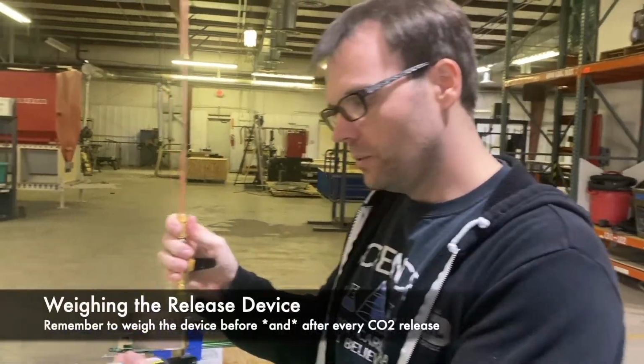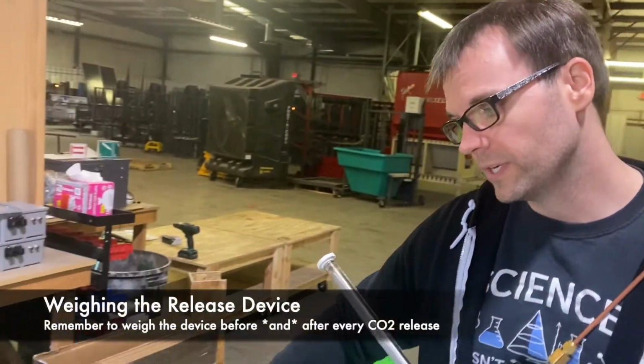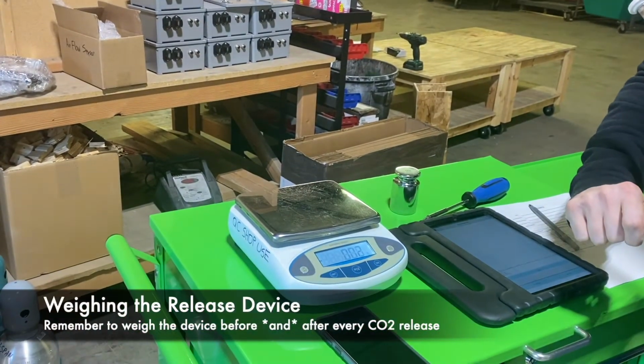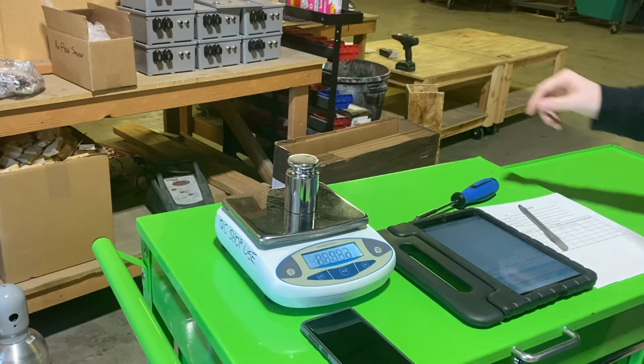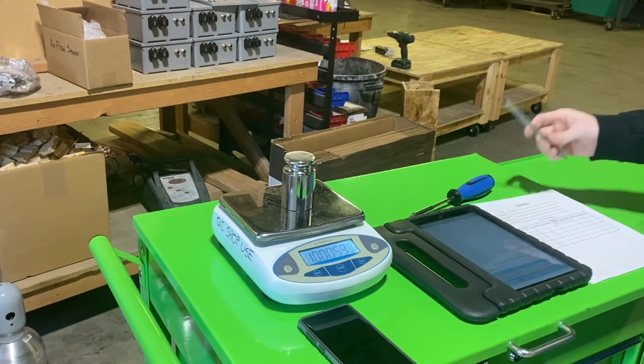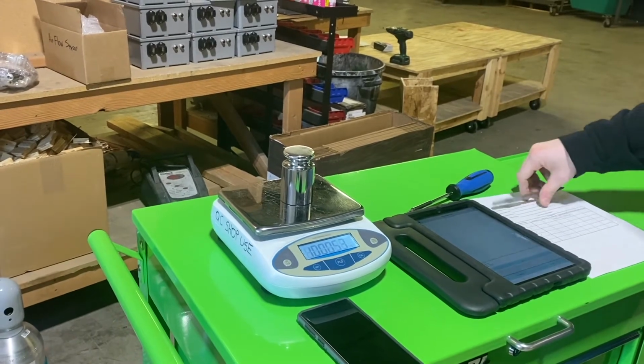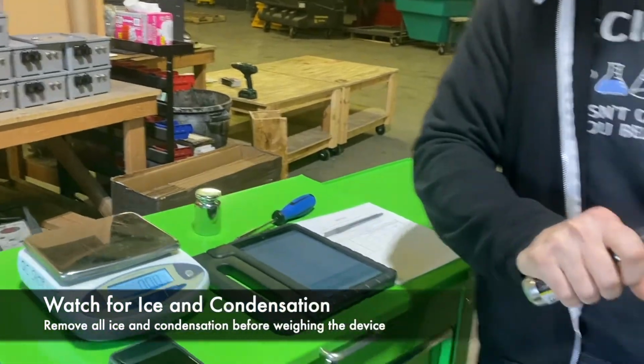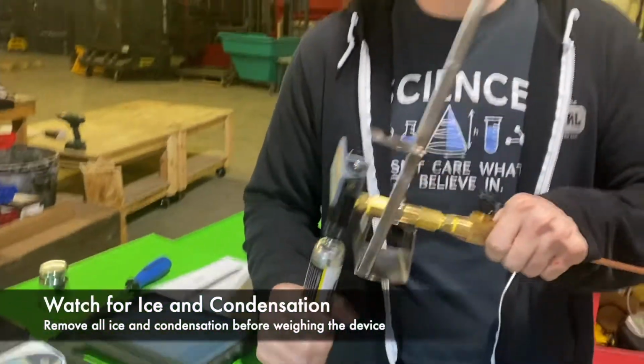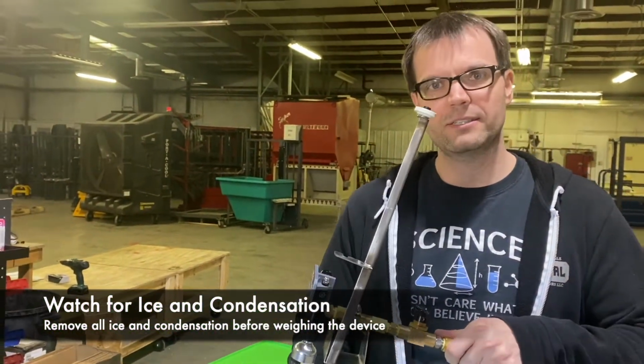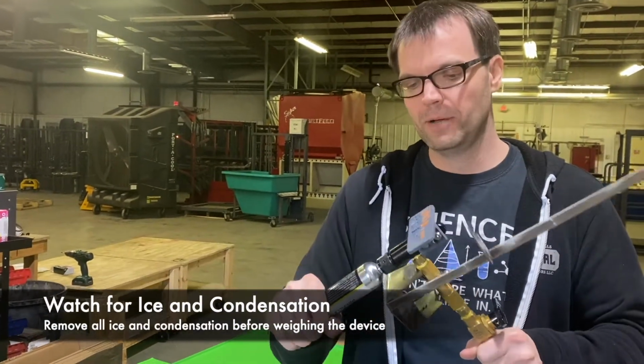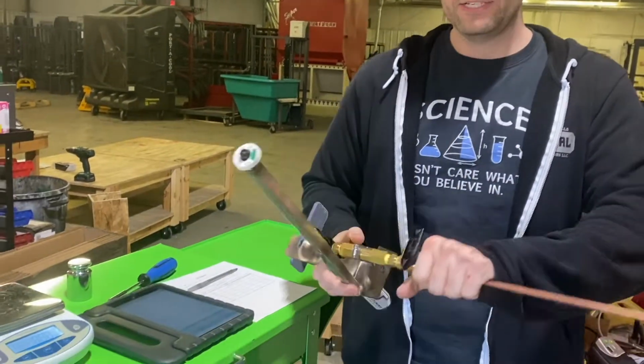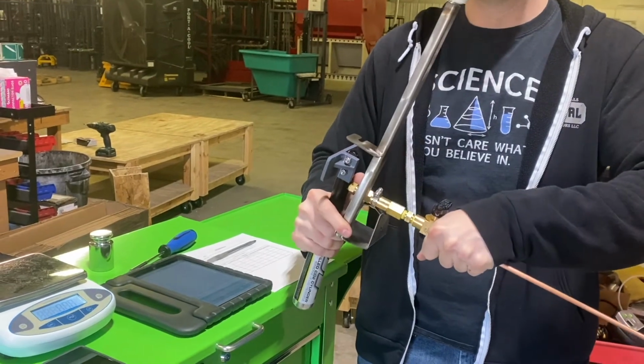All right, so now we're going to weigh this again, but first we want to make sure our scale's working. I'm going to tare it again. And now I'll take my calibration weight, and we should be reading the exact same number, 1000.53, so we're okay. And now one thing I do want to mention, because of adiabatic cooling, since we're releasing compressed gas into a gas, this is going to get very cold. And it's almost ice cold to the touch.